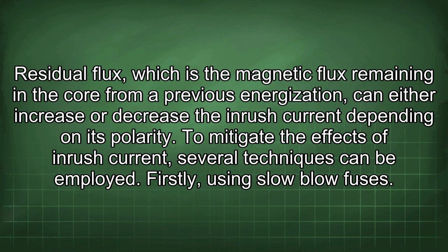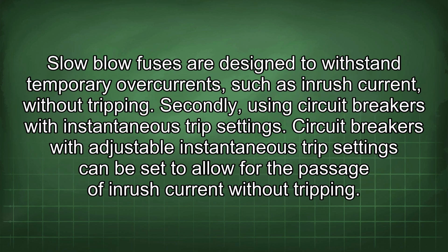To mitigate the effects of inrush current, several techniques can be employed. Firstly, using slow blow fuses. Slow blow fuses are designed to withstand temporary overcurrents such as inrush current without tripping. Secondly, using circuit breakers with instantaneous trip settings. Circuit breakers with adjustable instantaneous trip settings can be set to allow for the passage of inrush current without tripping.